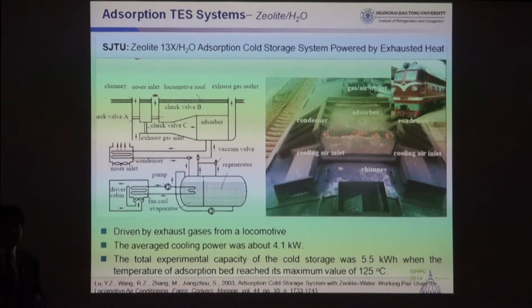So there's a storage tank for thermal storage in this case. During the generation or desorption phase, we could use the cooling effect stored here for output. During adsorption we have enough cooling, so in this case it can be stored in this cold water tank.